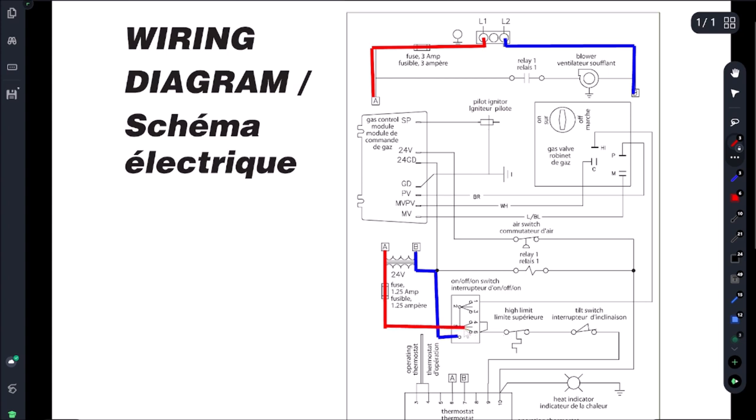Then the selector switch is going to close and then we're going to come through a high limit that's going to close, and then our tilt switch. The tilt switch wants to make sure the skillet is in the down position.